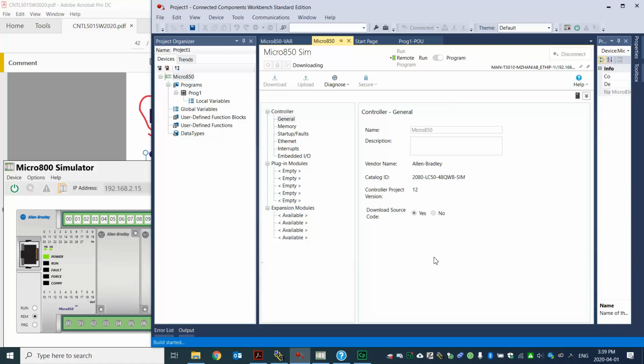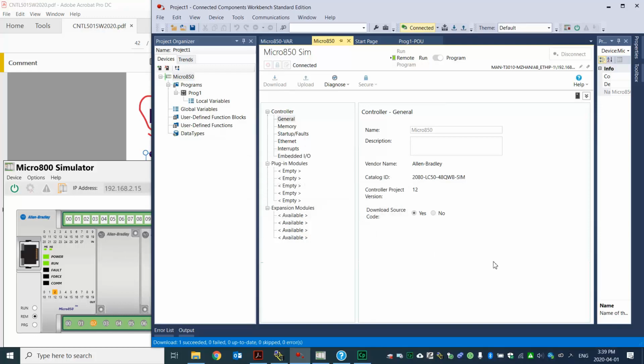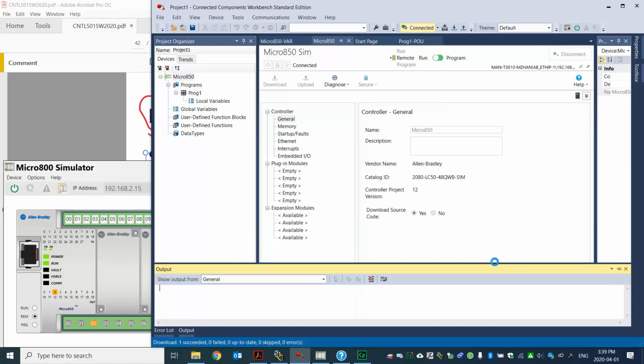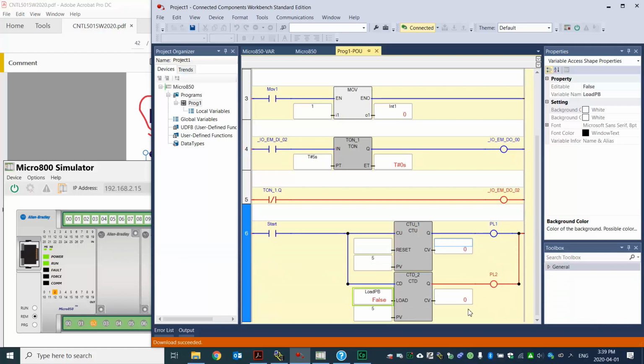Okay, let's see how it works. Basically, we create a trigger to set the current value as the preset. So over here, yeah, the trigger is false, it's 0. So if I highlight here, Control T, true. Notice here the current value is set to the same value as the preset value 5. So now if we toggle back, we already have the 5 on the current value.